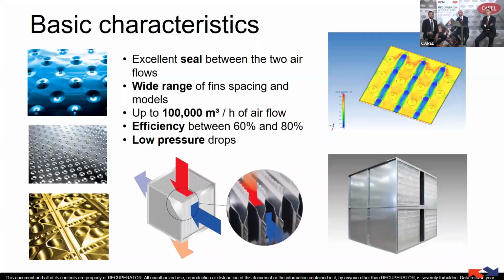Just a few words about the plate heat exchanger characteristics. A plate heat exchanger is a static heat recovery component composed of different plates combined together, which creates gaps where the air can pass through and release heat to the opposite airflow. In this way we have heat exchange without any type of cross-contamination.